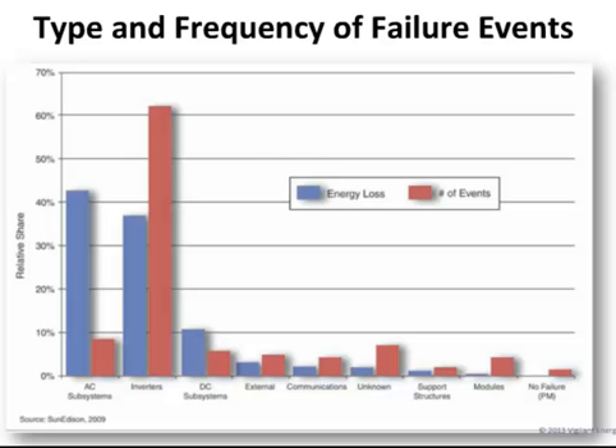Now let's see, 1, 2, 3, 4. The fifth over is communications. Our experience is that communications is a much higher incidence of alerts or failures. And that may be just because the alert levels that we're choosing to program may be more sensitive than that which SunEdison uses. Also, they have their own proprietary in-house monitoring package, so they may have been able to refine their product much better to keep their communications failures down. So kudos to them for doing that.